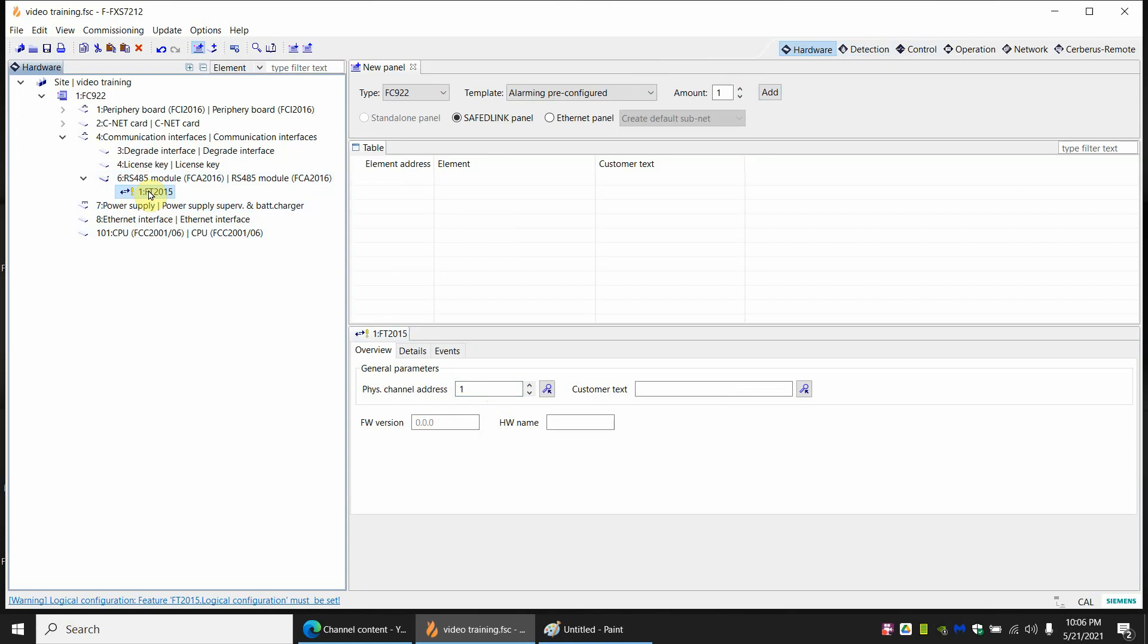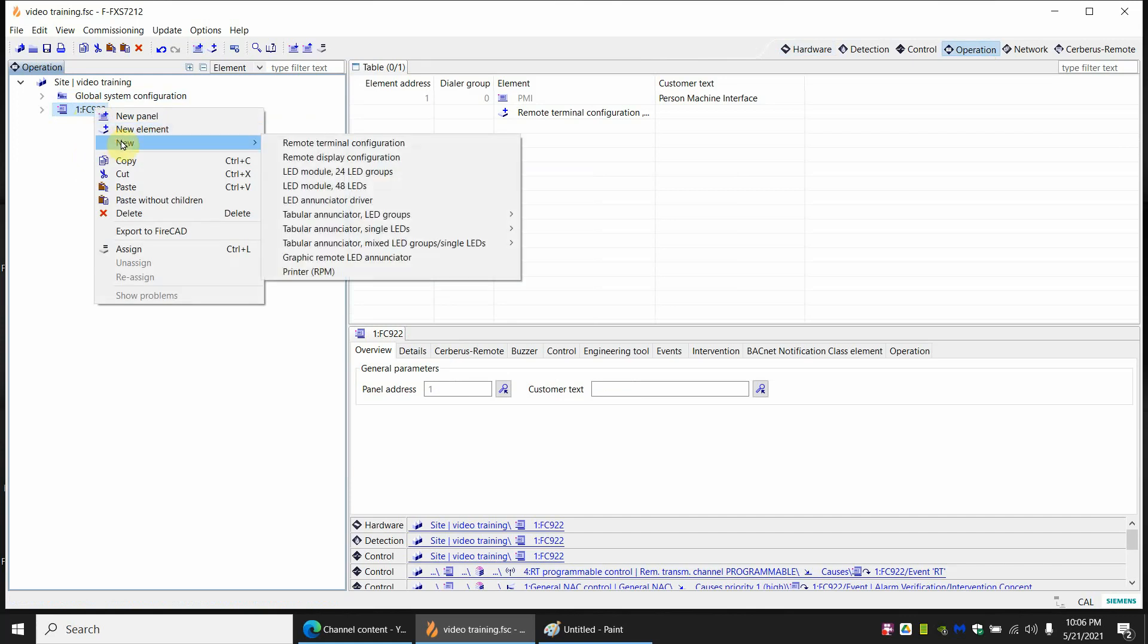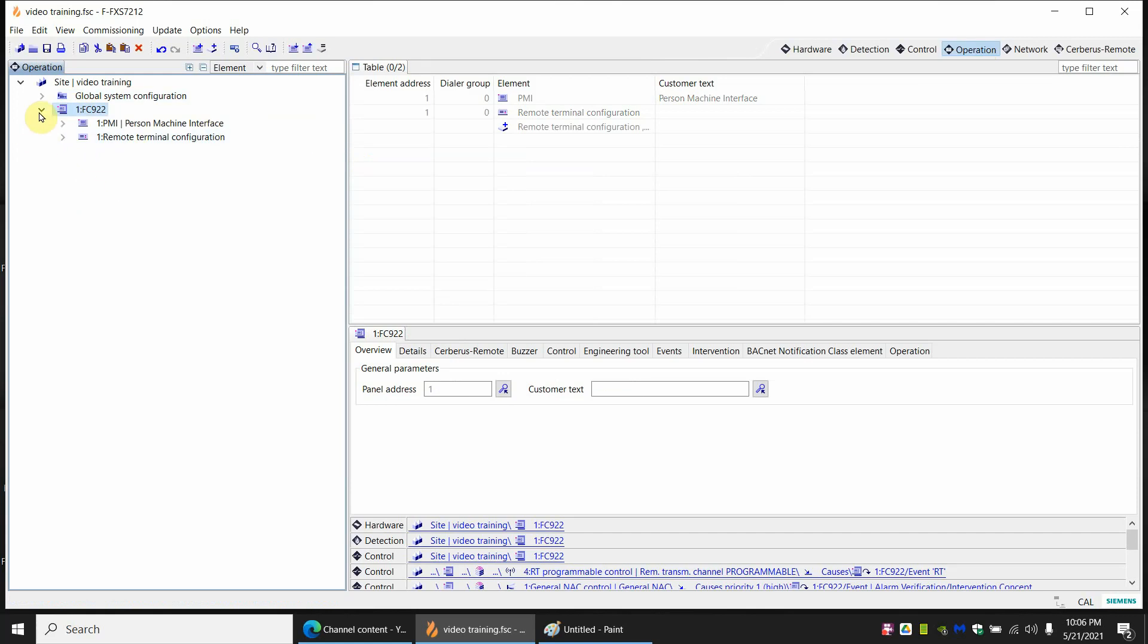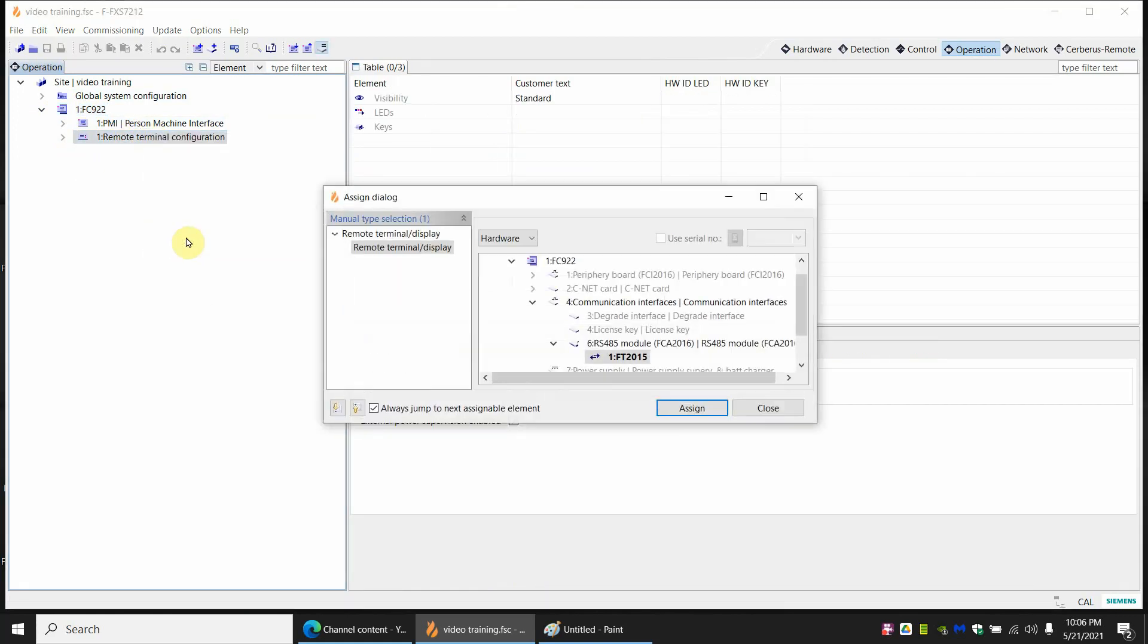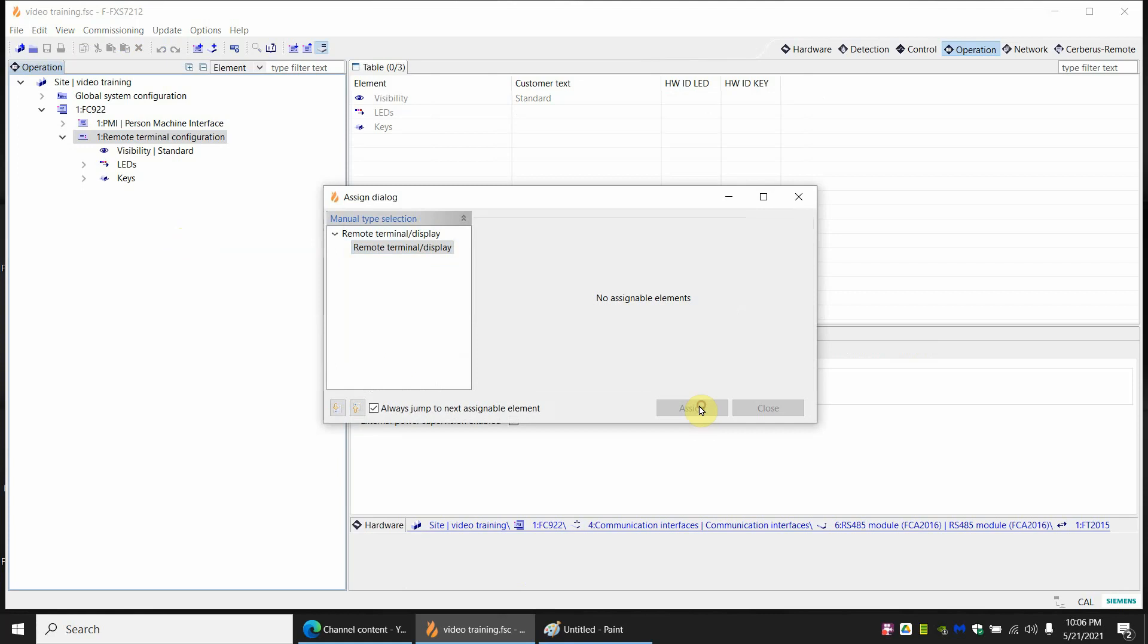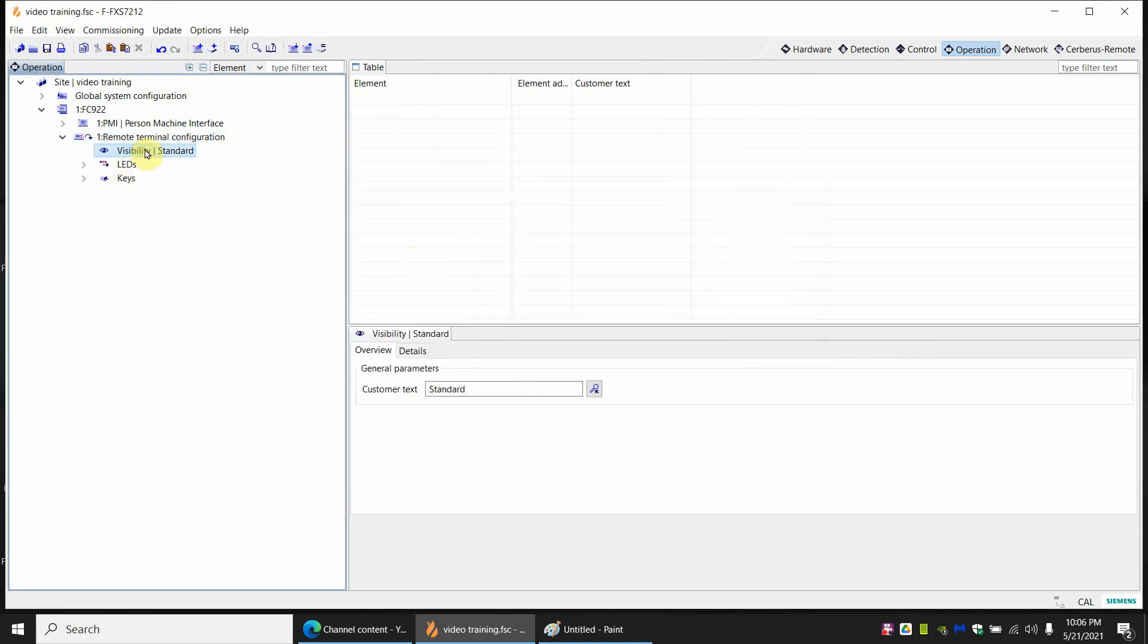To add a function to this we're going to go to the operation tab. Now here you show your multiple panels. In this case I only have one panel, the FC-922. We're adding enunciator to this. So we're going to right click on the 922. New. And there's a remote terminal configuration. Now opening this up a little more, you see it has the PMI and it has a remote terminal. Now you might have a multiple remote terminal. So you have to assign this still. So click on remote terminal. Right click and assign. And it should appear. There it is, an FT-2015. So you can have multiple and you pick the right one. So address one is the one we want for this.